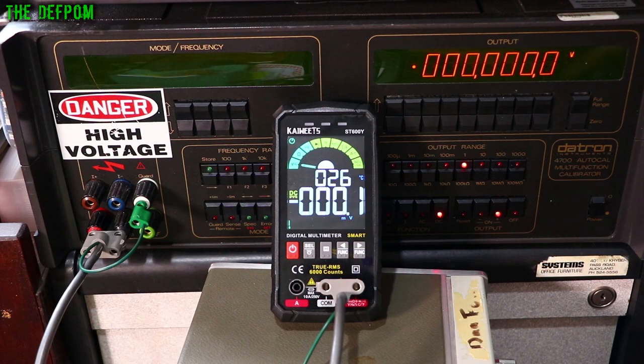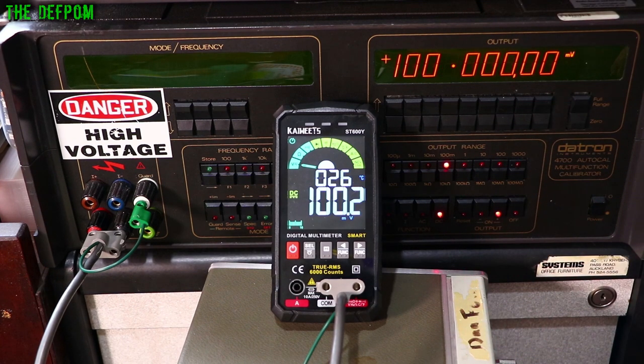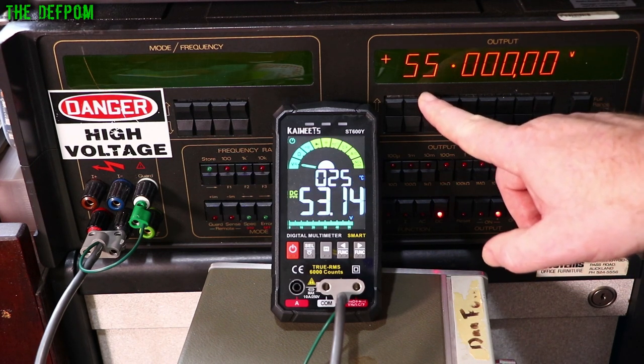Here at the calibrator, starting with DC voltage. At 1V DC: about 3 counts out. At 100mV: 2 counts out. At 10mV: 1 count out — but in the opposite direction, which is interesting. At 1mV: 1 count out. At 10V: 3 counts out. At 100V: 1 count out. Checking the top end of the 6,000-count range at 55V: 16 counts out. On the 6V range: 18 counts out. On the 600mV range: 15 counts out.